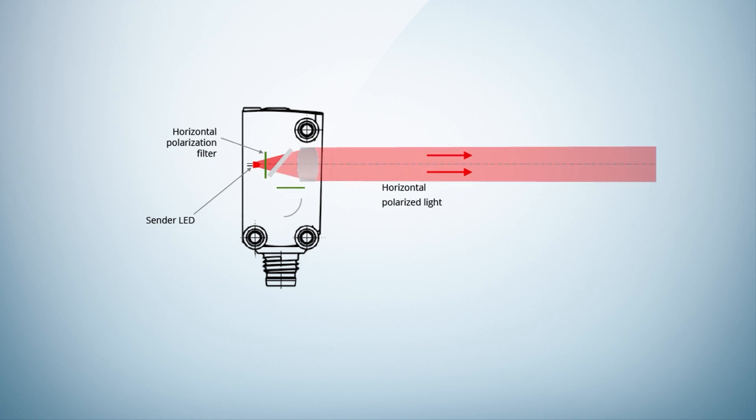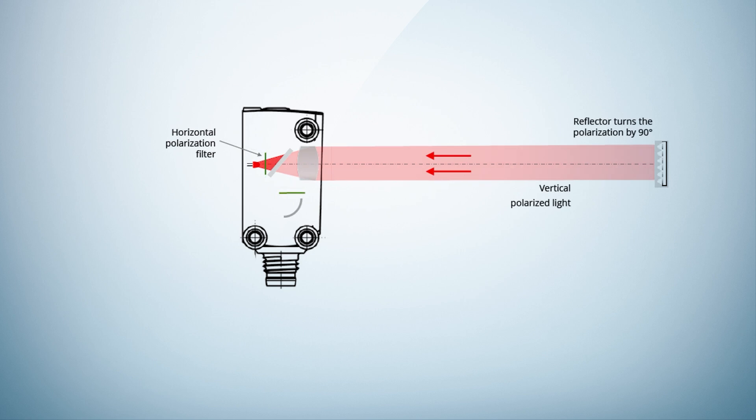Sender light passes through a polarization filter, which polarizes the light horizontally. The polarized light is reflected by the reflector. During this process, the polarization is rotated by 90 degrees. The light is now vertically polarized.